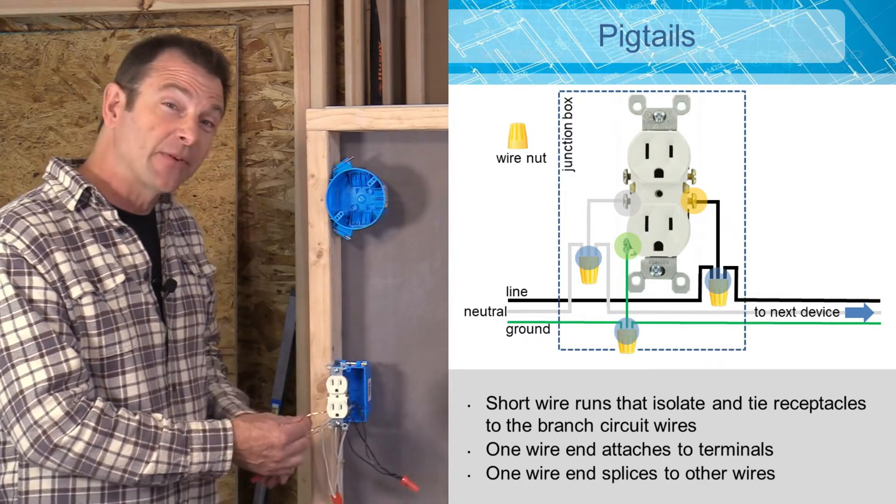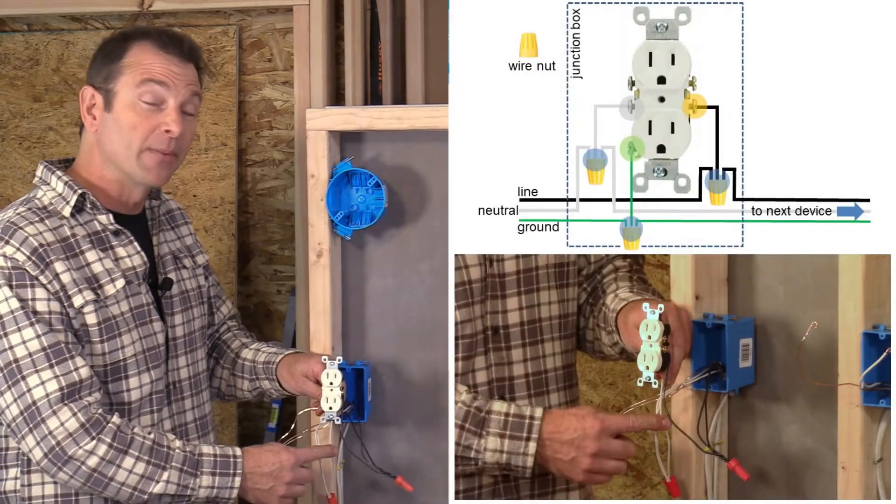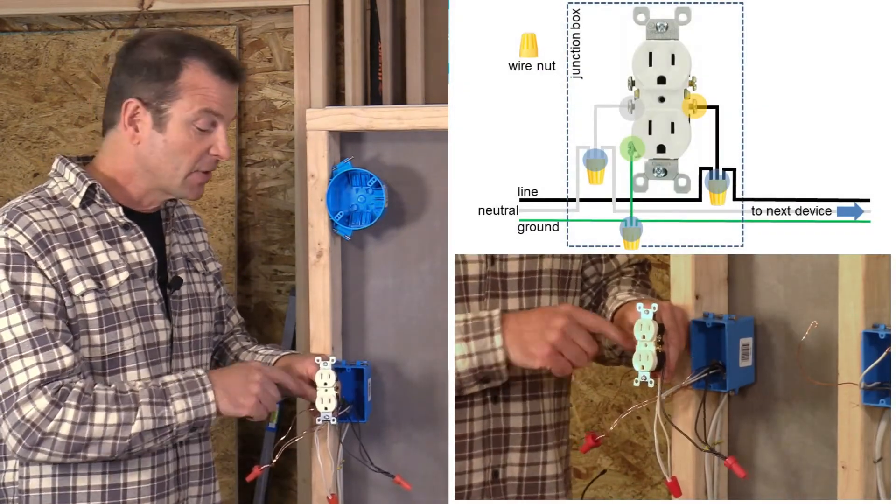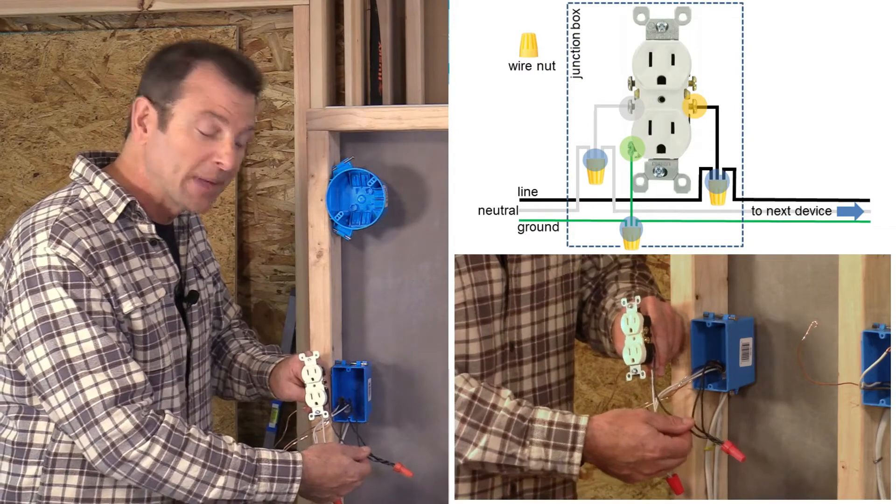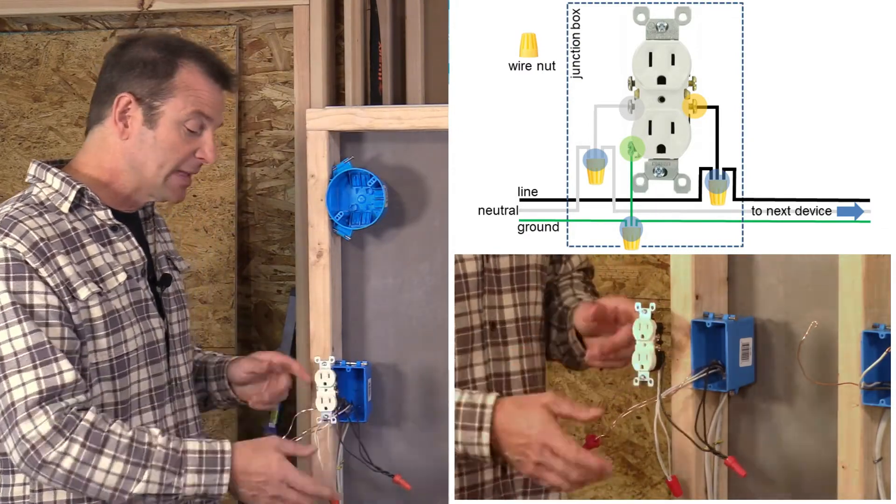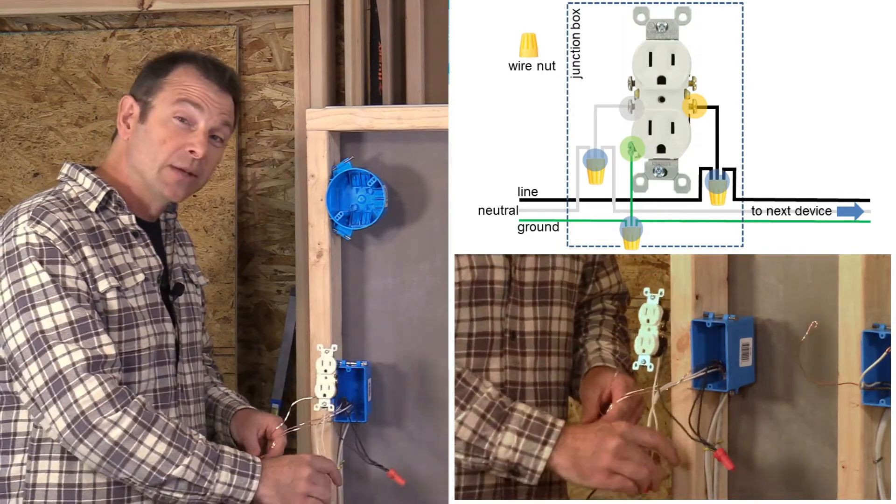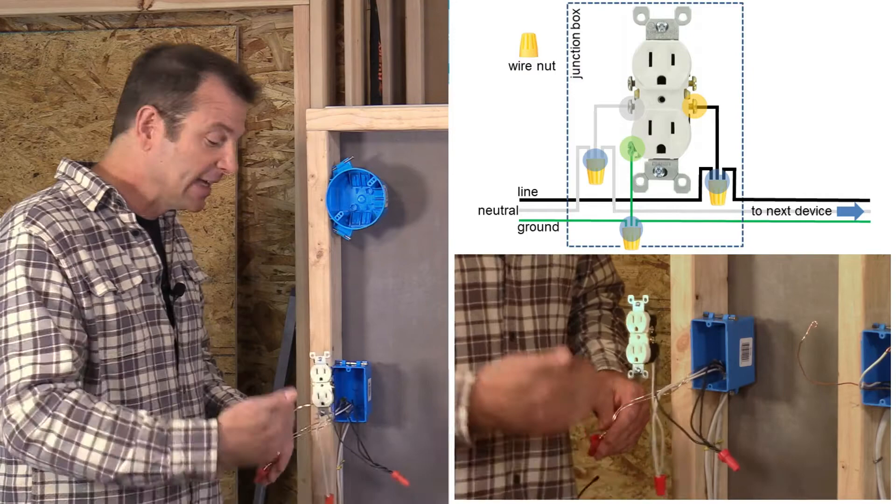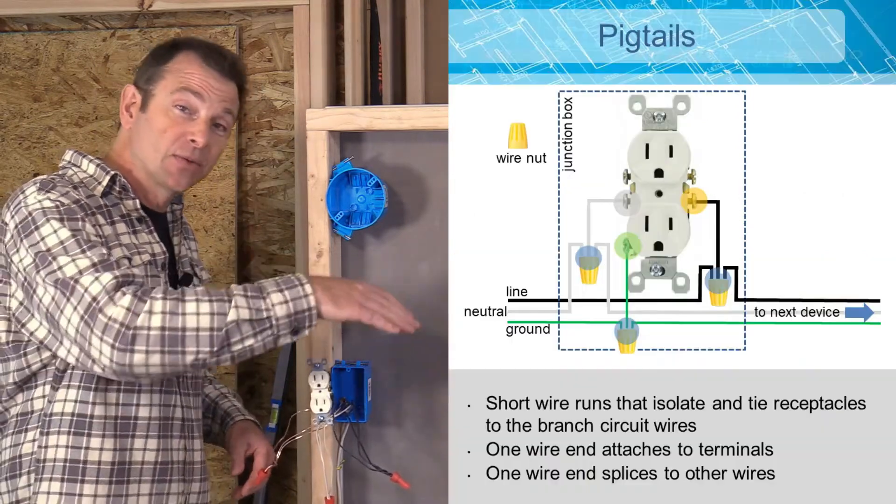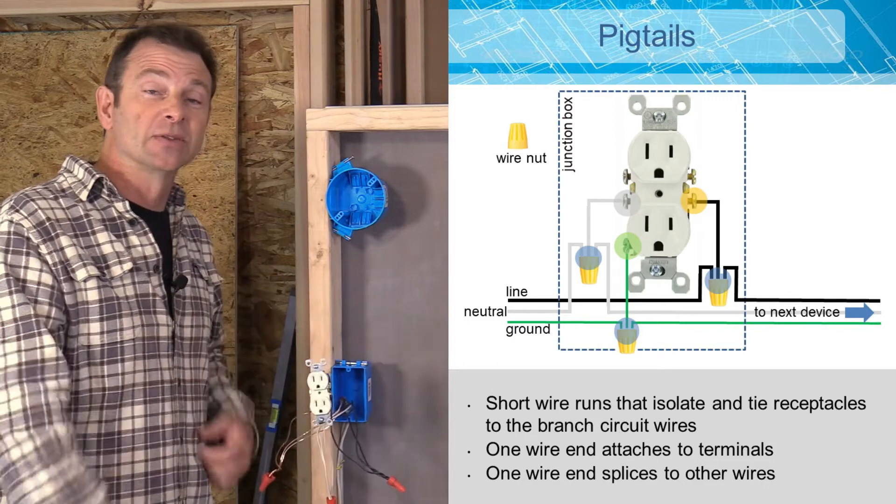Those are all getting connected to a short wire we're calling a pigtail. I've got a pigtail for my ground that's going to a ground terminal. I've got this short pigtail for my neutral going to the silver terminal. And I have a short pigtail for my hot going to my gold terminal. So you see here we have three terminals that are connected to two other wires. And this allows us to continue through this circuit and isolate this outlet from all of those connections.